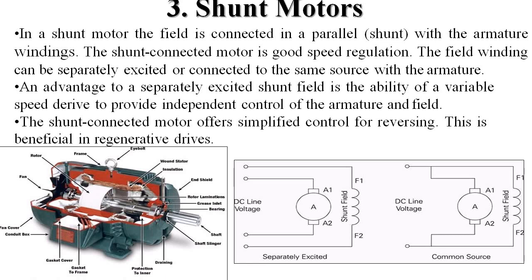An advantage of the separately excited shunt field is the ability of a variable speed drive to provide independent control of the armature and field. The shunt connected motor offers simplified control for reversing. This is beneficial in regenerative drives.